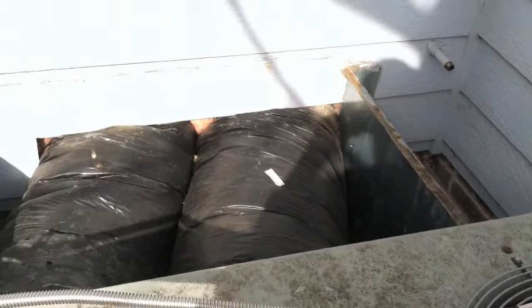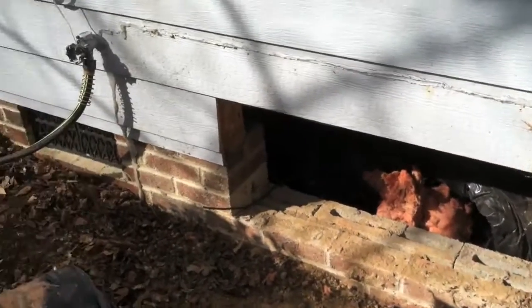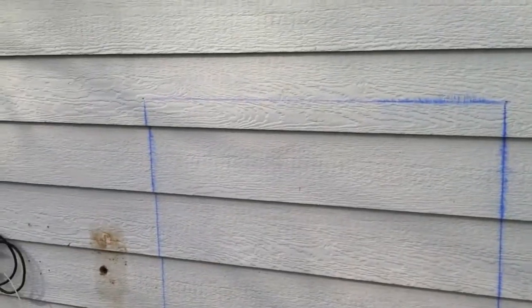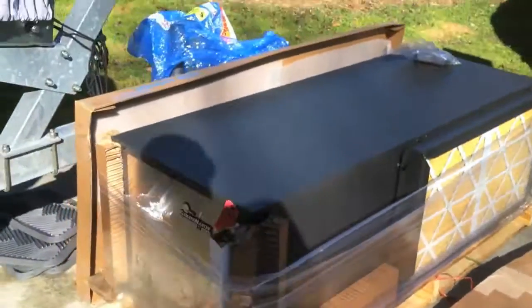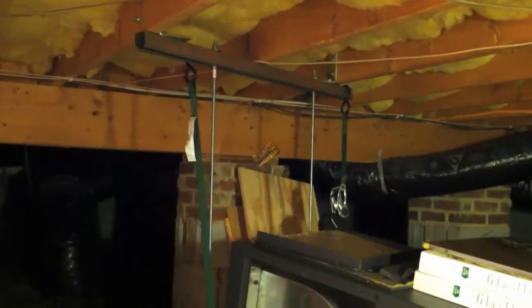Here's my old gas pack unit that I replaced — supply and return duct work coming out through the wall. I removed all that. I already had a header in my crawl space, so I was able to cut out that section of the wall to give me good access into the crawl space for maintaining and installing the unit. The ClimateMaster unit was delivered on a pallet and I was able to put it on a hand truck to bring it into the crawl space.